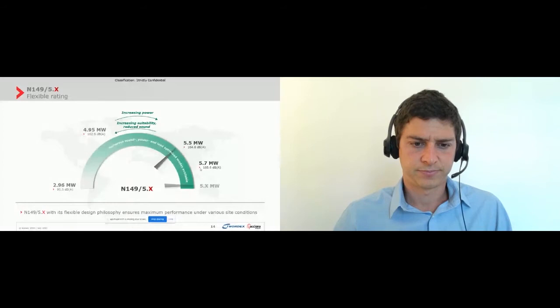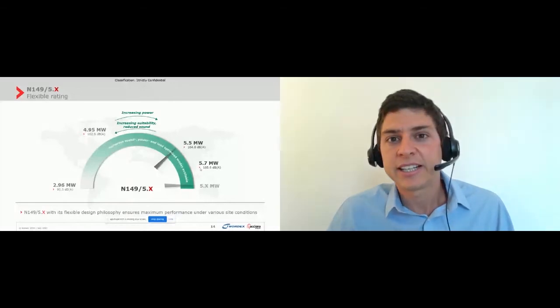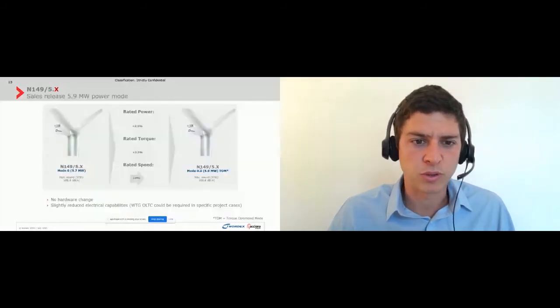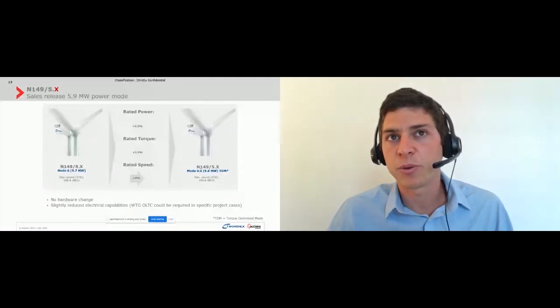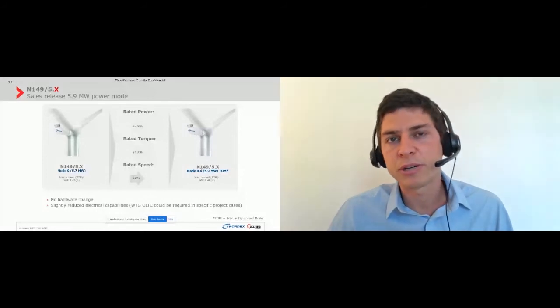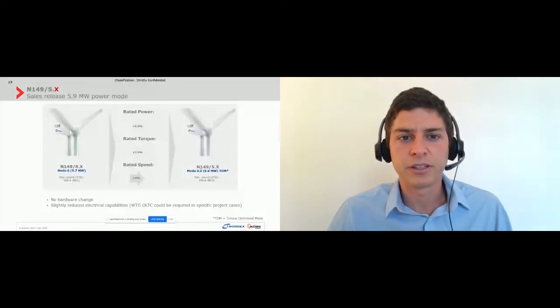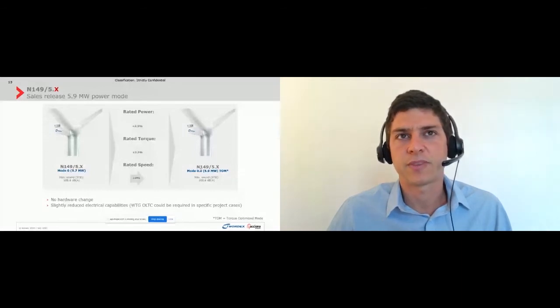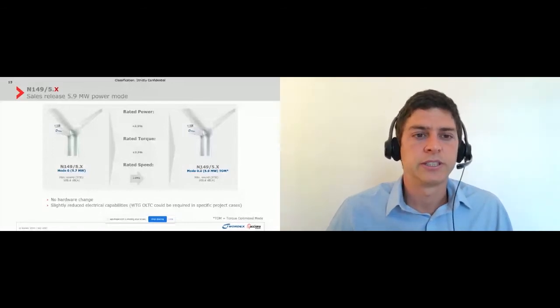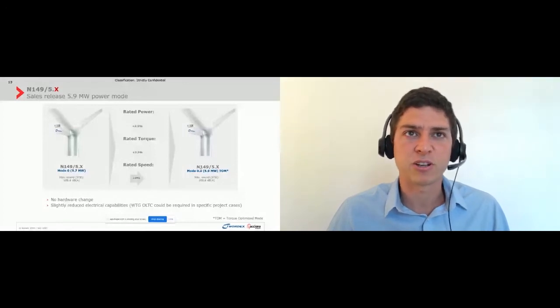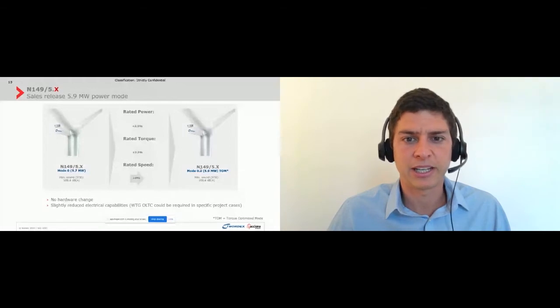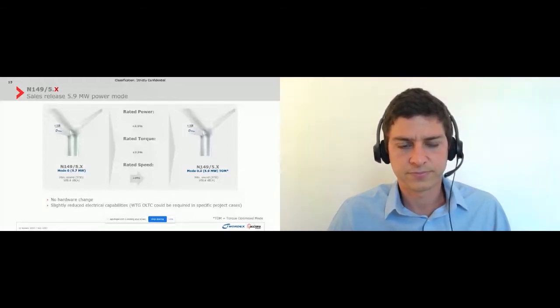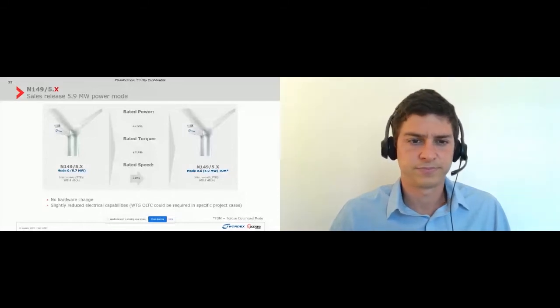A comment here, Patricio, to complement. One can come to believe that, in a site of 10, 11 meters per second, it would not be feasible to install the 149 mode 5.7, but the truth is that what we are seeing is that the machine is extremely robust, and if the turbulence conditions allow it, we could reach maximum power modes, even with very elevated wind speeds. This machine we have been able to place at nominal power in sites of up to 11 meters per second. We do not necessarily have to lower too much in nominal power. That was to note that, so that the robustness that the platform really has can be seen.